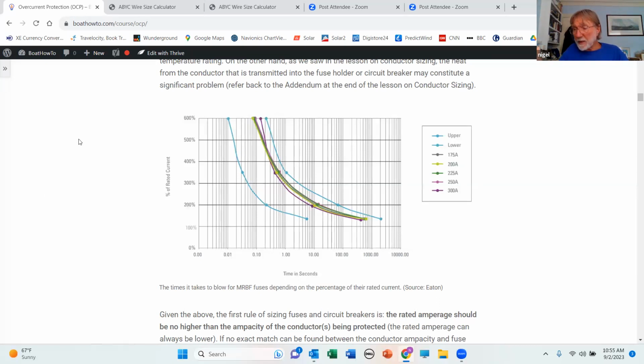You take a bigger battery, like a group 24 AGM battery, one that's physically about this size, rated at 200 plus amp hours. You put a dead short across that, it can deliver 3, 4, 5,000 amps for not a very long period of time, but you can get huge amps out of it. You take a lithium-ion battery. I was just looking at some statistics yesterday for a dead short on a lithium-ion battery. It was 13,000 amps. And we're fairly certain that some of these bigger lithium-ion installations could be 15, 20,000 amps. So a fuse has a rating for the maximum number of amps it can safely interrupt in that dead short circuit.